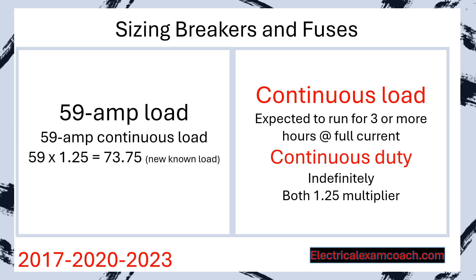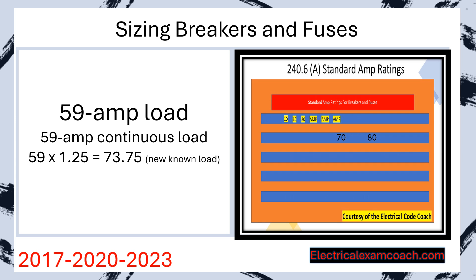Let's take our 59 amp known load from before and imagine it was told to us as a 59 amp continuous load. What we would do is take our 59 amps and multiply it by 1.25. That gives us a new known load of 73.75 — the 59 is gone, and 73.75 is our new known load. We'd head to Table 240.6A, look at the next standard size above 70, which jumps to 80, and we would put this on an 80 amp overcurrent protective device.